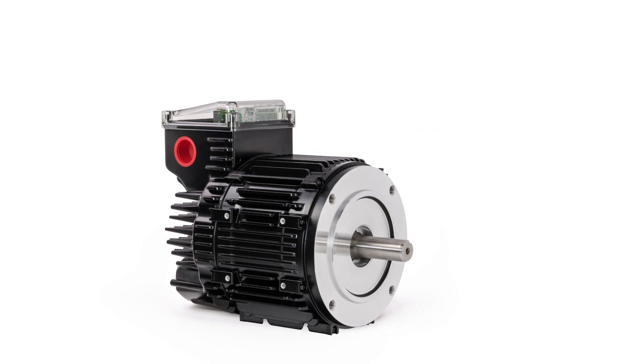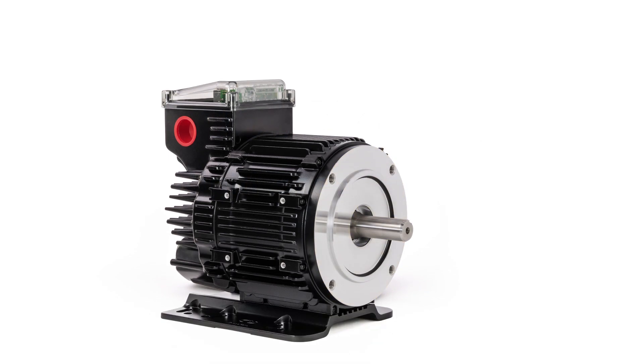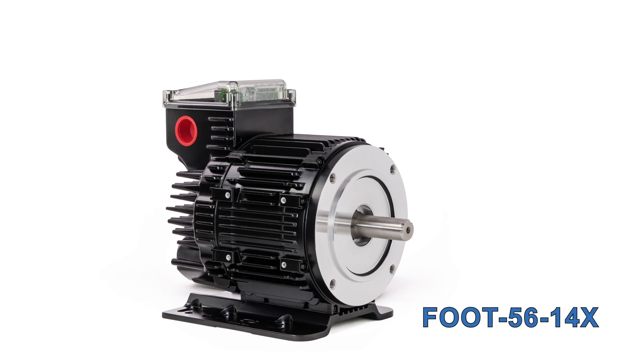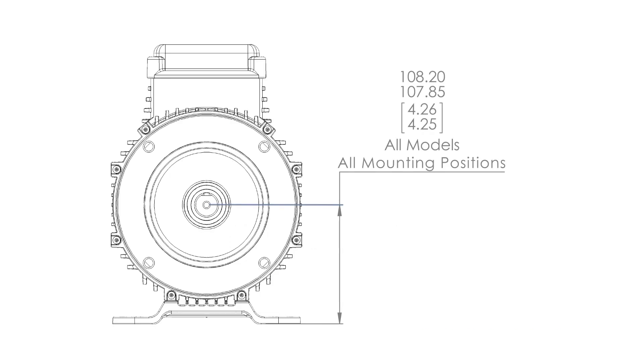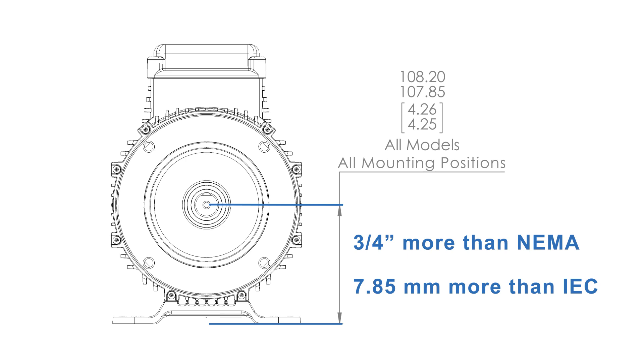In addition to standard face mounting, ClearPath integral horsepower motors can be foot mounted using the cast aluminum rigid base foot mount accessory. The foot can be attached to any of the three sides not occupied by the junction box. Note that the shaft center is 4.25 inches from the mounting surface of the foot—three-quarters of an inch more than the standard for NEMA 56 and NEMA 143 motors, and roughly 7.85 millimeters more than the standard for IEC 100 frame size motors.